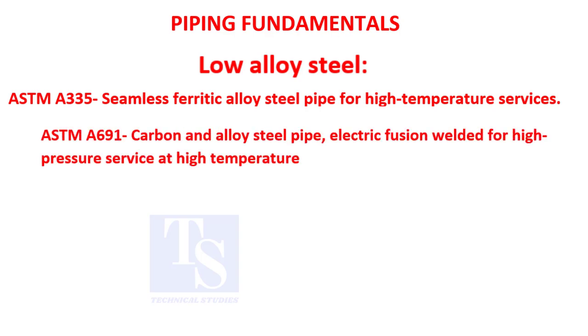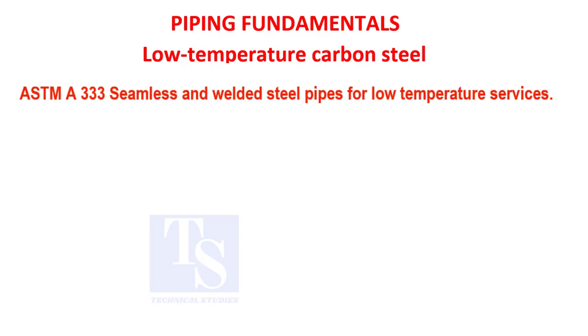ASTM A-691: carbon and alloy steel pipe, electric fusion welded, for high pressure service at high temperature. ASTM A-333: seamless and welded steel pipe for low temperature services. ASTM A-671: electric fusion welded steel pipe for atmospheric and low temperature services. Available sizes are larger than 16 inches.